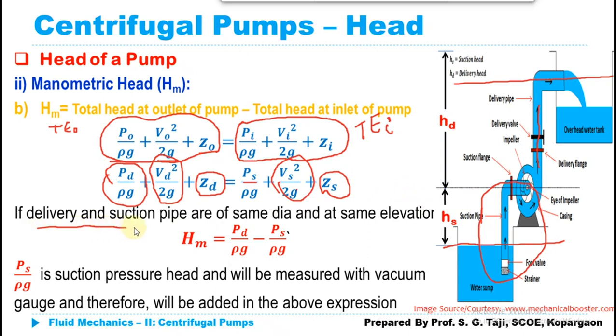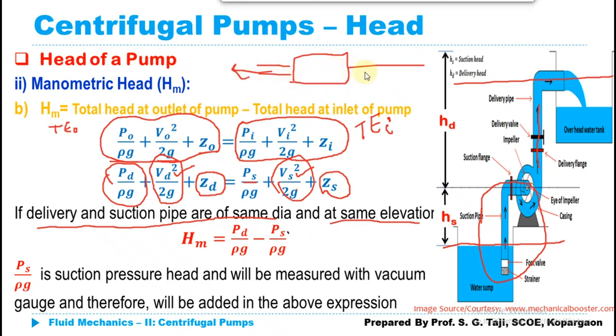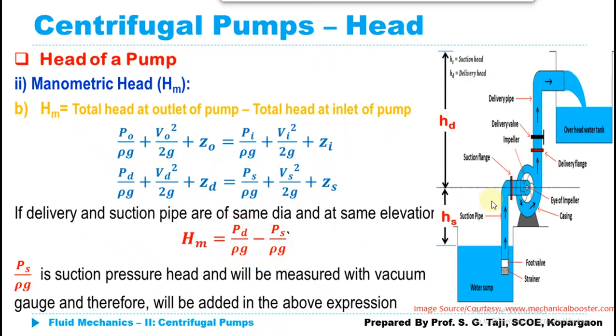If the delivery and suction pipes are of the same diameter, then VD squared upon 2G and VS squared upon 2G cancel each other. And if both are at the same elevation — for example in a horizontal pump arrangement with a suction pipe and delivery pipe at the same level — the manometric head reduces to PD upon rho G minus PS upon rho G. Since the suction head is measured by a vacuum gauge and is negative, the negative-negative becomes positive, so the manometric head is the pressure head in the delivery pipe plus the suction head.